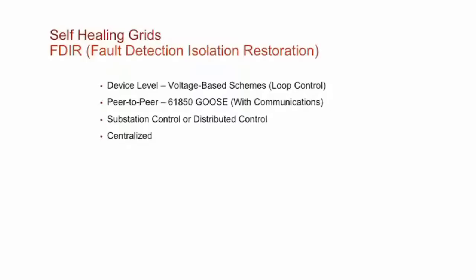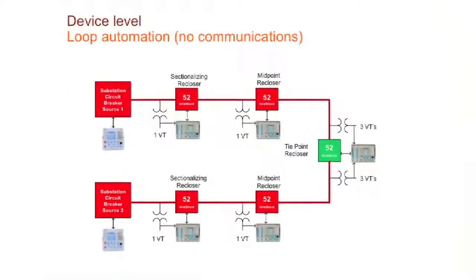So, talking a little bit about why these requirements are important. I talked about communication, flexibility, open protocols. So why is that important? You could start deploying distribution automation schemes, and a lot of customers might fall into one of these 4 categories if they consider doing FDIR schemes. FDIR is fault detection, isolation, and restoration. So you might be on a device level, based on voltage. You might be going to peer-to-peer communication, using communications obviously. Or substation control, which we call distributed control, where you have a gateway at the substation that collects all the information from the remote devices and has the logic to perform switching and restoration, doing a lot of calculations to see what's the best route to restore power. Or centralized, and when we say centralized it's a DMS system that looks at the whole system.